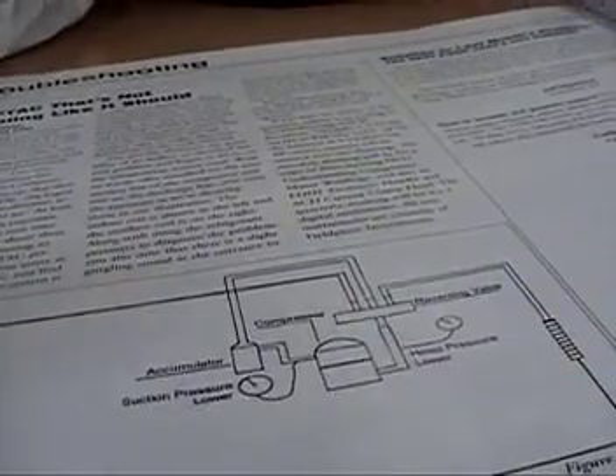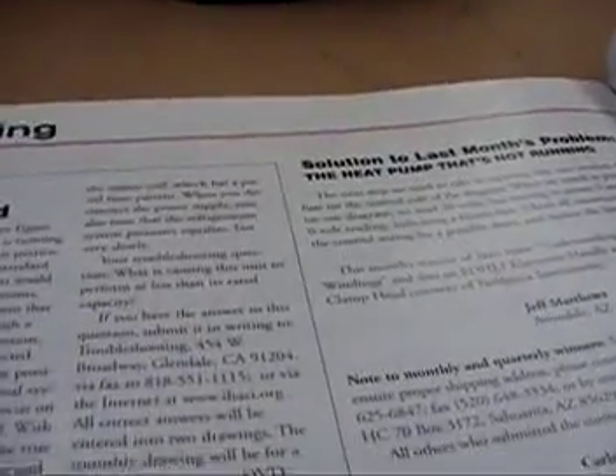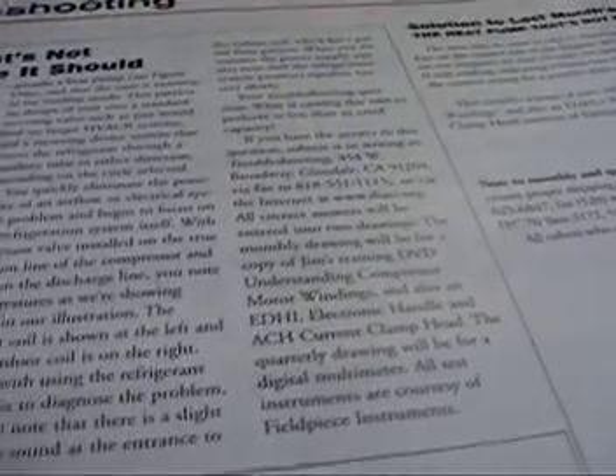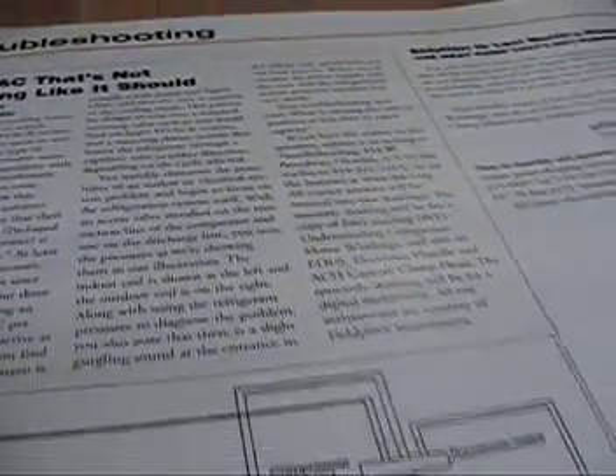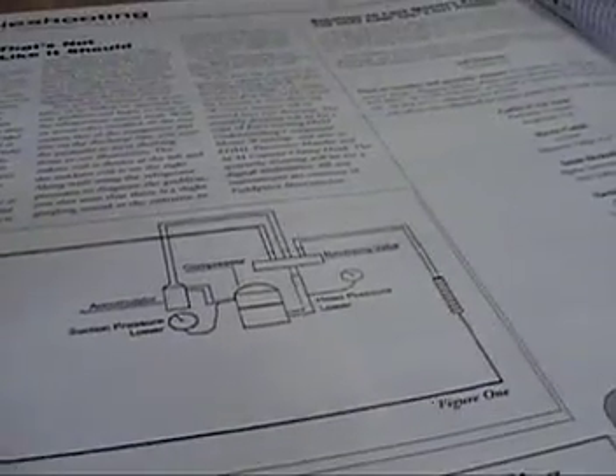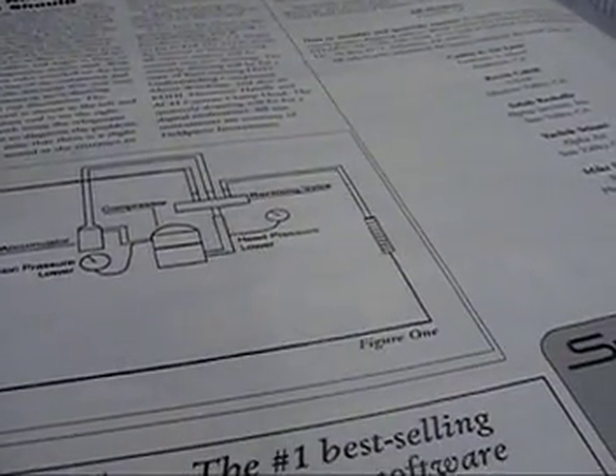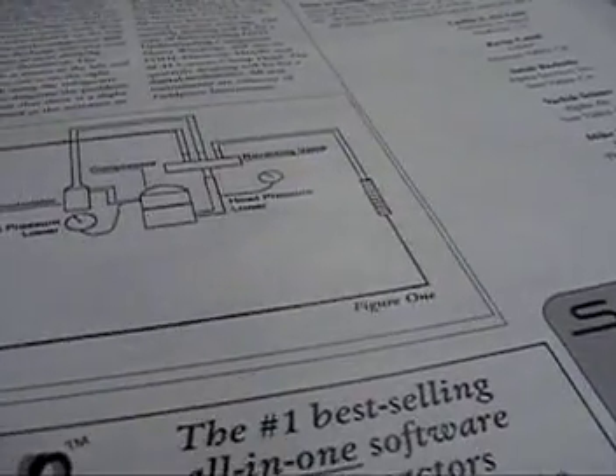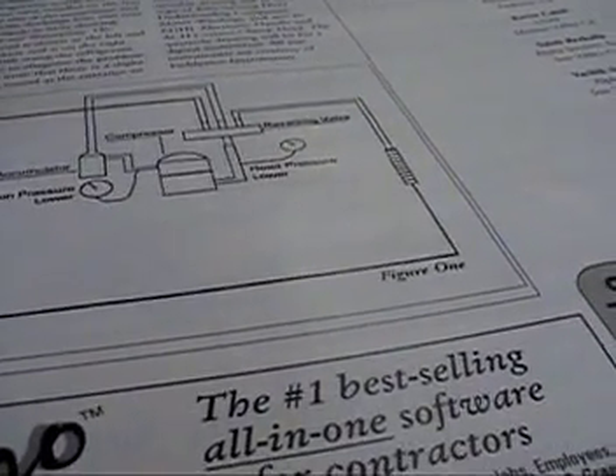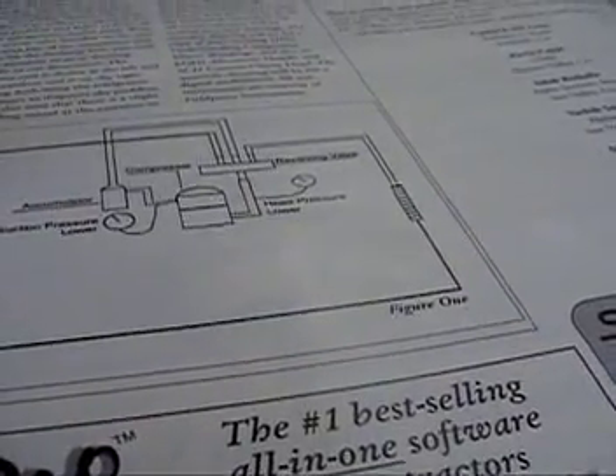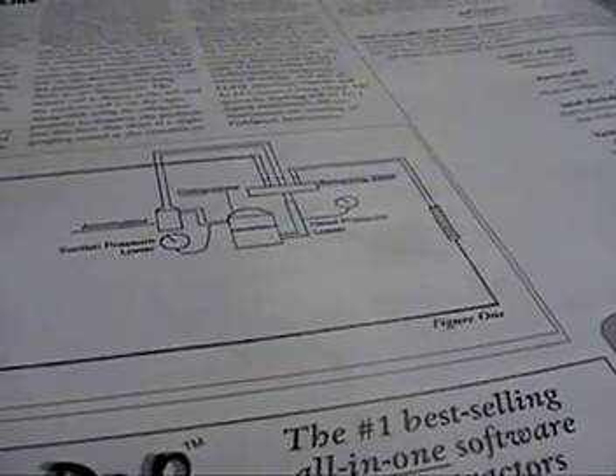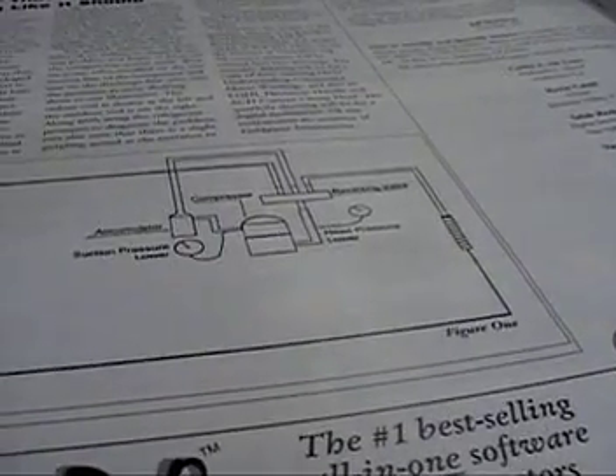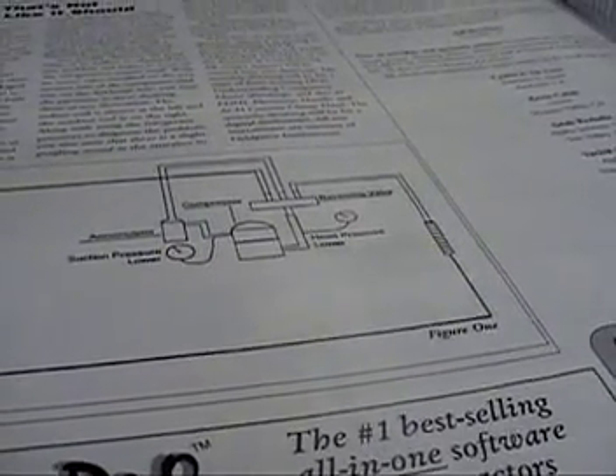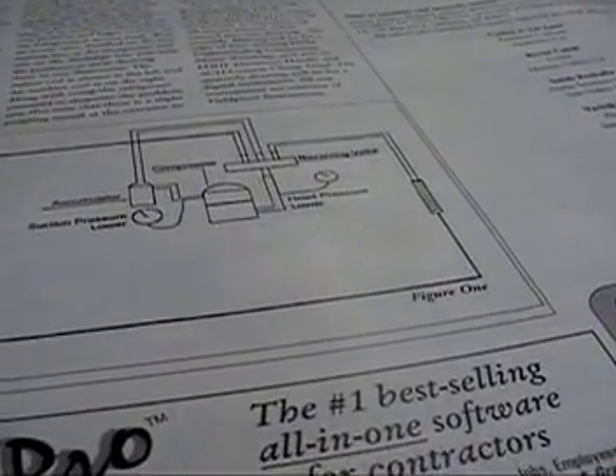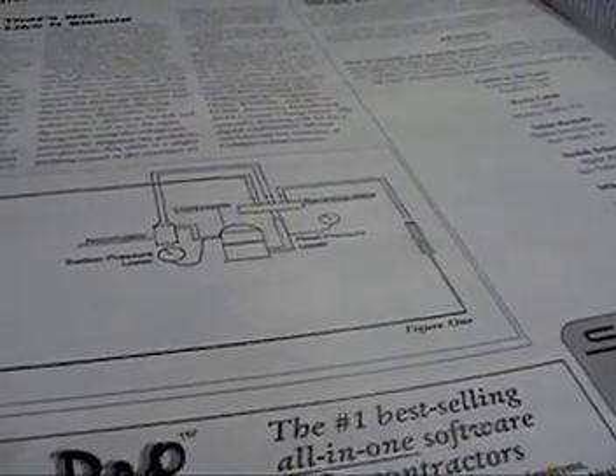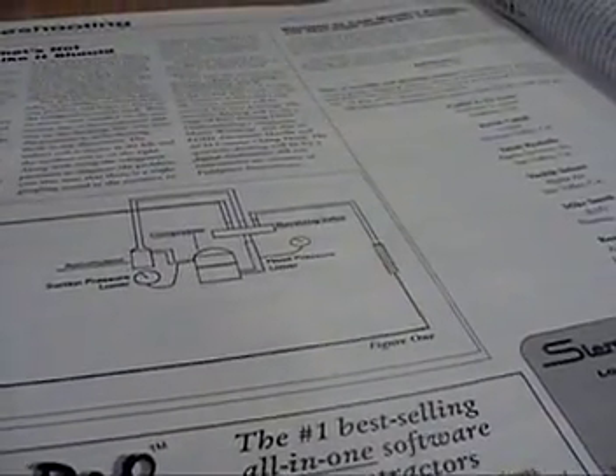Let me see. Pressure diagnosis of the problem. You also note that there is a slight gurgling sound at the entrance to the indoor coil, which has a partial frost pattern. When you disconnect the power supply, you also notice the refrigerant system pressures equalize, but very slowly. Your troubleshooting question: what is causing this unit to perform at less than its rated capacity? God, that didn't give you much to go on, did they?